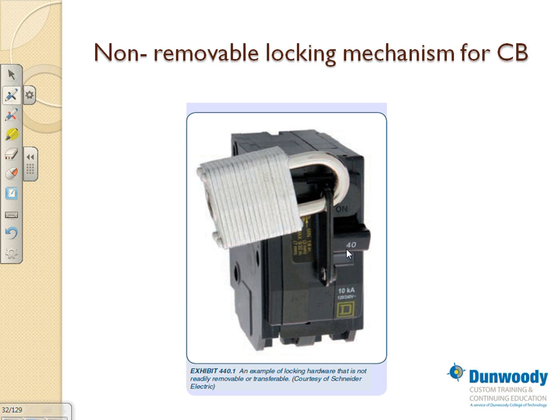Locking. Your disconnect has to be able to be locked in the open position, and the locking mechanism has to stay in place regardless of the lock. I don't know if you remember, you guys use these portable locks when you're working on a lighting fixture like this, you can go to the panel. You don't have to disconnect. It's better to disconnect it because that's where they came up with that little disconnect for these double-ended fluorescent lights. But if I want to troubleshoot this receptacle here, or change it, I don't have by code to disconnect it. Well, it's a good idea to disconnect it.